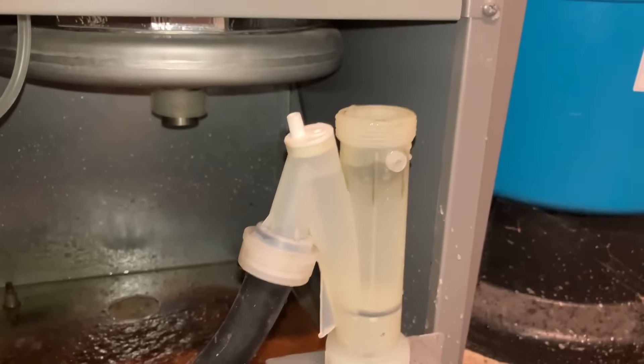Take two — I wasn't at the right level of elevation, so now I am carefully, slowly pouring water into the top of the condensate trap. I'm going to repeat that until this fills with water, and it drips out of there. And there it is — dripping out of that three-quarter inch 45.